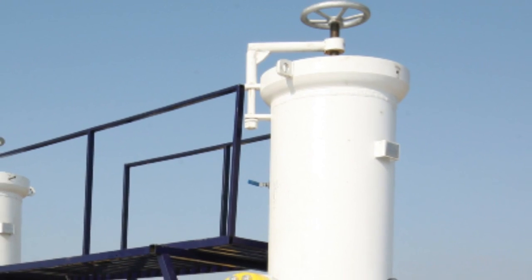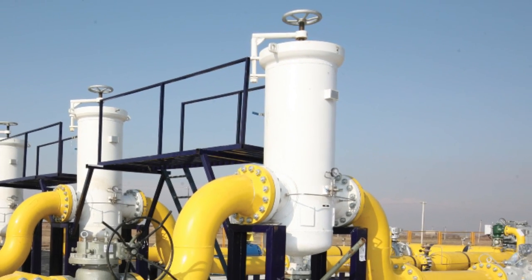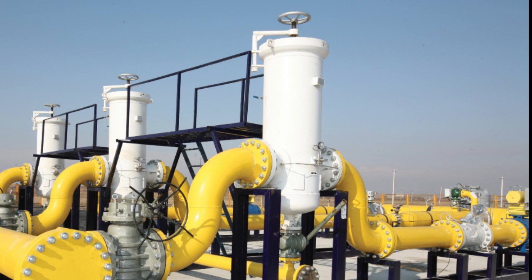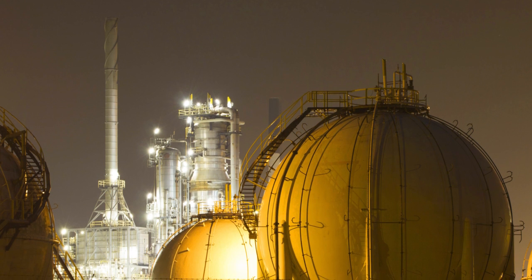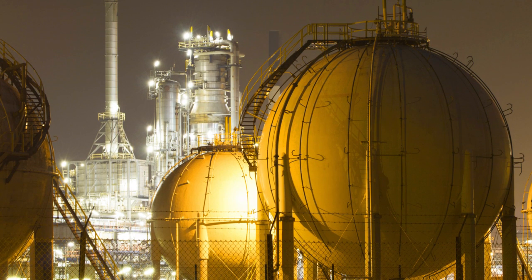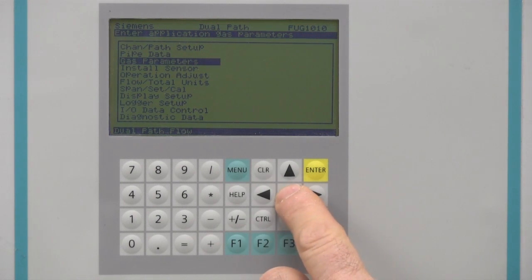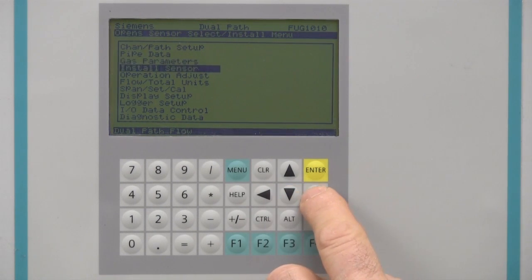The SITRANS FUG1010 is designed to operate on natural gas pipelines. The FUG-1010's gas data menu is therefore pre-configured for natural gas flow measurement and the values should be perfectly adequate for most applications. In part two of this video series, we will cover gas parameter settings and standard volume measurement in detail. For now, we may proceed with the commissioning of the meter by advancing directly to the install sensor menu.